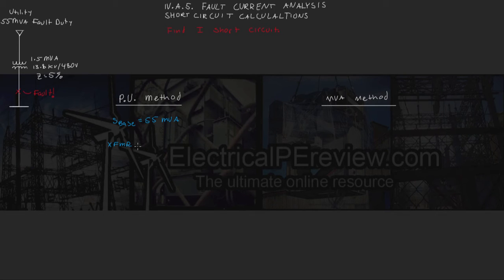Our transformer's fault duty per unit is going to equal our transformer value, which is 1.5 MVA, divided by its impedance, which is 0.05. Next we're going to use the base up here we selected. We're going to divide the value we get by 55 MVA. This comes out to a transformer fault duty of 0.5454 per unit.